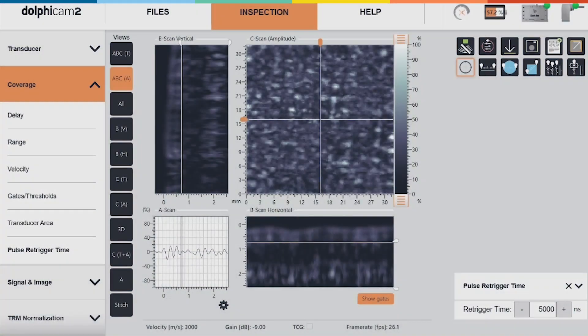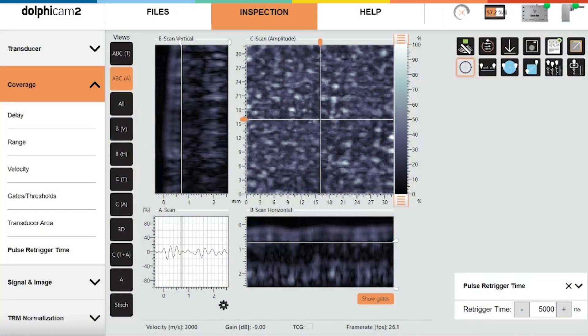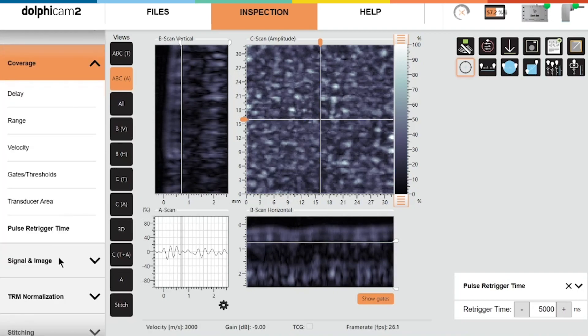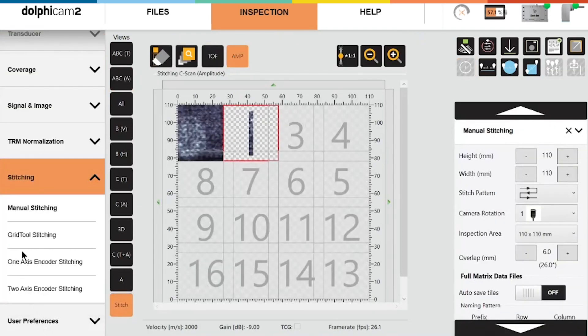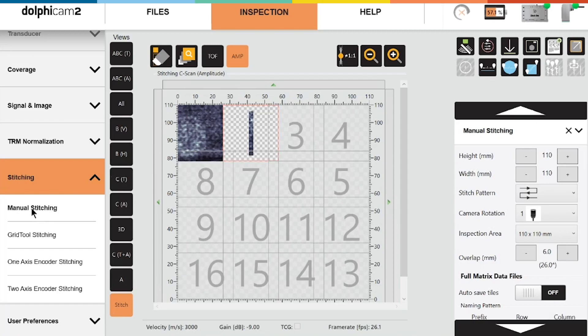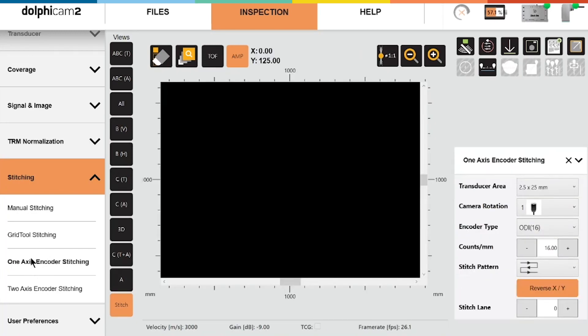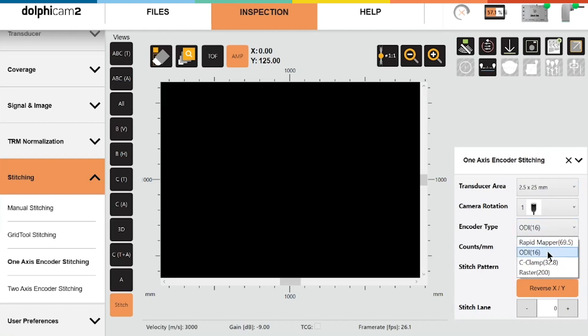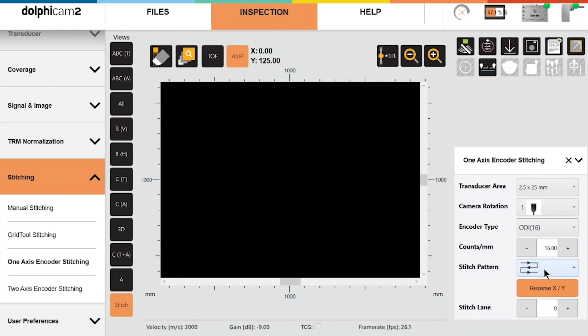Coming over to my software, if I'm happy with the setup I can come through to the stitching menu. I'll click stitch here. I don't want to do manual stitching today, I want to do one axis encoder stitching. The encoder type we have a preset for ODI. The 16 means that it's 16 counts per millimeter so it's going to get the correct distances. I'm happy with this stitch pattern, it's a raster pattern going backwards and forwards.